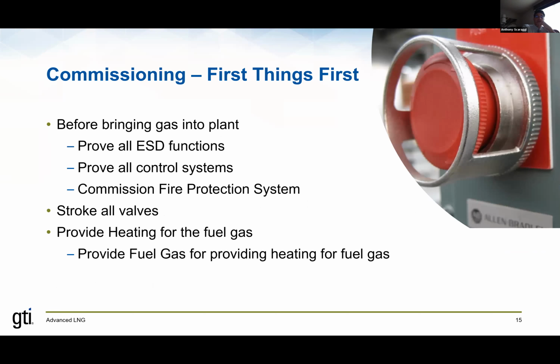The very first thing you do in commissioning is you bring all the safety systems online. So before you introduce gas into the facility, you make sure that your shutdown systems are all working, tested, and proven. You prove that all the control systems operate as they're supposed to operate. The valves open and close as they should. And that's what this means here, stroke all valves. And you commission the fire protection system, which is the system that was installed based on the analysis of your facility that was done very early on, to determine where all the gas detectors and smoke detectors and whatever items are necessary for your facility. Those are all installed, and that whole system is commissioned.